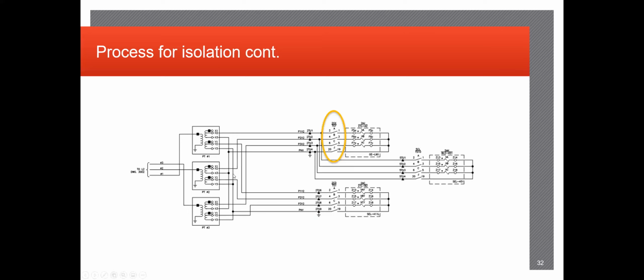So identifying, we haven't looked at these yet. We looked at the current circuits, but we haven't looked at the voltage circuits for those relays. But this is an example of the set of PTs coming off the high side going into the relays, and each of them that are associated with it. So again, it's pretty self-explanatory, but you've got voltage coming off of the low side, goes through the relay and is grounded back out and back on the PTs. So each of them has an identifier for each phase. So you've got your A phase, your B phase, your C phase coming off of each one of these PTs.